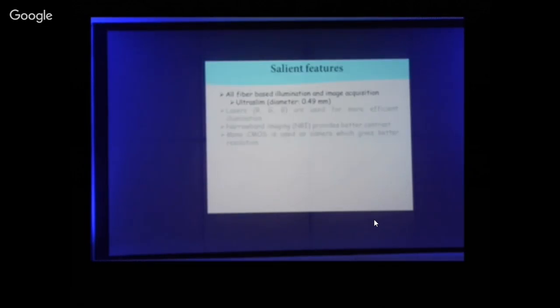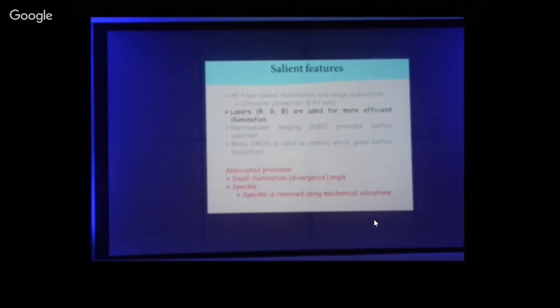Okay, so some salient features of this endoscope are that we are using all fiber-based illumination and image acquisition. There are 20 illumination fibers of NA 0.57, leading to an aperture angle of 70 degrees, and an imaging fiber, a high definition image guide of 10,000 pixels. It has a focal distance of 5 millimeter and a viewing angle of 65 degrees. Secondly, as I said, we are using an RGB laser for more efficient illumination.